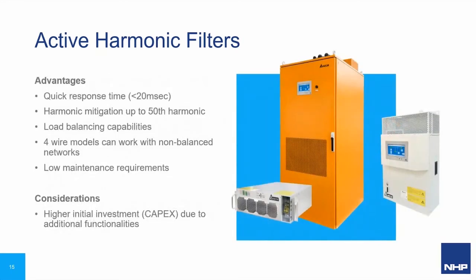So, same advantages as before: the quick response time of less than 20 milliseconds to any changes in the waveform. They provide harmonic mitigation of up to the 50th harmonic. They can provide load balancing capabilities. And in particular, the 4-wire models work with non-balanced networks and compensate for that. And again, not a whole lot of moving parts, therefore low maintenance requirements. Your consideration, again, is that higher initial investment due to additional functionalities. I'm going to talk about that a little bit more now.